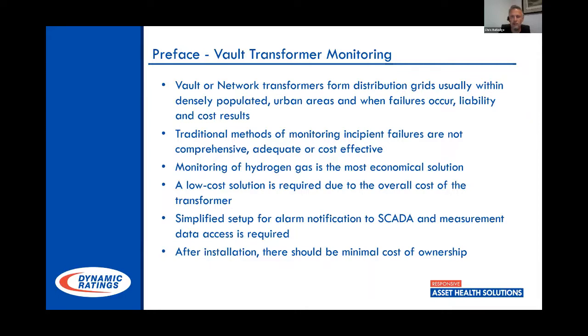So PD was one option I had looked at. Of course, that was really hard to find in a price range that was going to be effective. And so I ended up going with hydrogen monitoring. However, everybody's hydrogen monitor seemed to only be for the main tank, and I just wasn't seeing enough failures occurring in the main tank. That wasn't where the bulk of my problems were coming from, but I definitely felt the monitoring of hydrogen gas was going to present the most economical solution for monitoring these. So also it had to be something that was a fairly simplified setup.